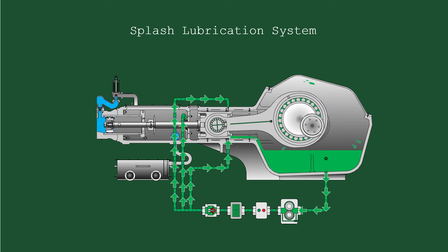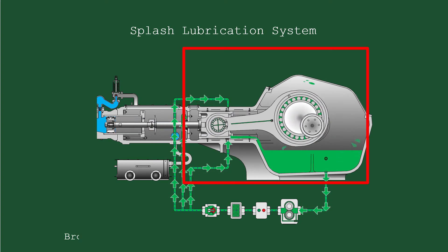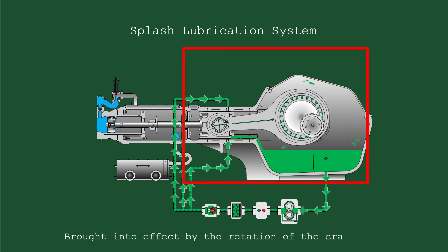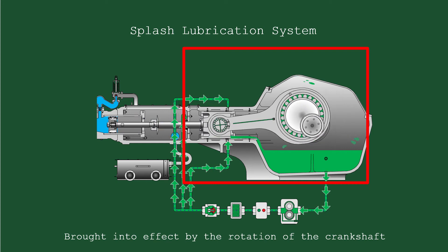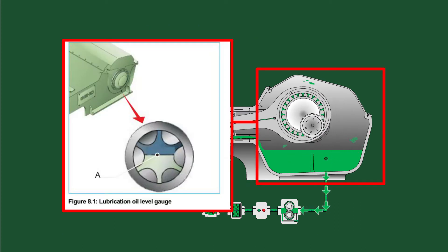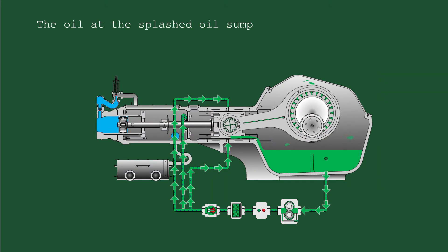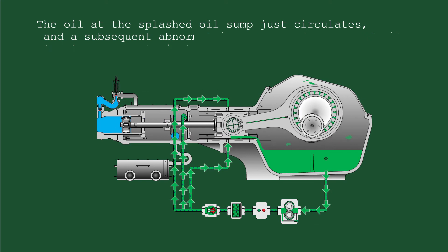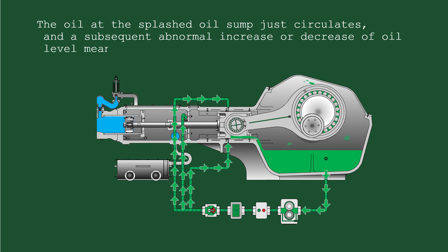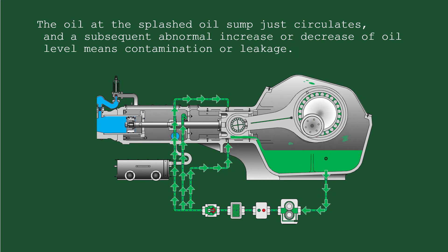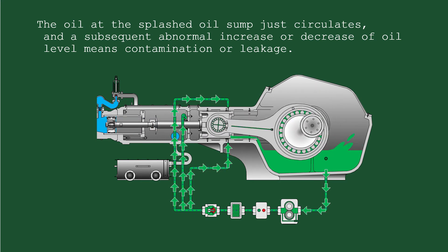The Splash Lubrication System used on the Crankshaft Bearings is brought into effect by the rotation of the Crankshaft in the Oil Sump. This causes the oil level fluctuation observed in the level gauge. The oil at the Splashed Oil Sump just circulates, and a subsequent abnormal increase or decrease of oil level means contamination or leakage and should be reported immediately.